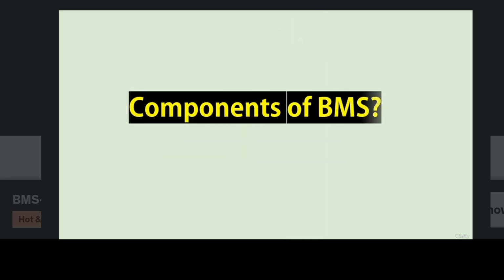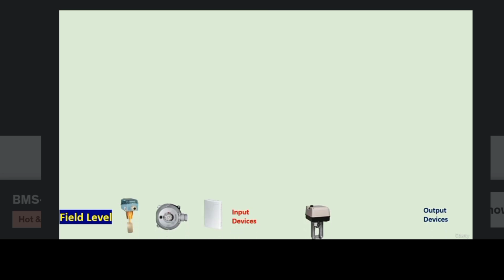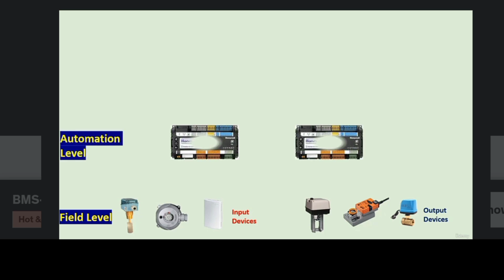Now let's talk about components of BMS. In terms of hardware, BMS consists of three different levels. First level is a field level which consists of input and output devices. Input devices can be sensors like temperature sensor, humidity sensor, carbon dioxide or carbon monoxide sensor, and contact closure devices are switches which can be differential pressure switches or water flow switches, and output devices can be actuators like damper actuators or valve actuators. Then we have automation level which consists of microprocessor based DDC controllers.